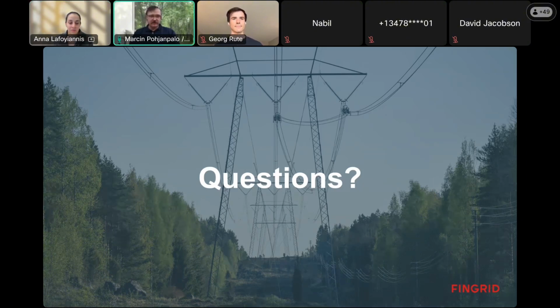In our case, we just assume the worst case situation for the whole line. Let's say we have 60, 70, or 80 centigrade on the whole line, and if none of the spans go below that, we're fine, because that's what defines our clearance. But as Georg said, you could do it span by span if you have certain spans which are more critical or more windy.